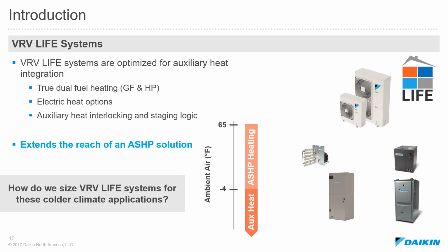So we've painted a picture of air source heat pumps being challenging in the North American market. How do we get around those challenges? Fortunately, we have VRV Life, which was designed specifically for the North American market with those challenges in mind. One of the best things about VRV Life is we're able to integrate a gas furnace and a coil. That traditional solution that most people in the residential industry are familiar with, we can easily integrate into a VRV Life system, have that operate during those peak days out of the year, so maybe a handful of days, and then use that highly efficient means to condition the home for the rest of the heating season. So it's a truly optimized system.